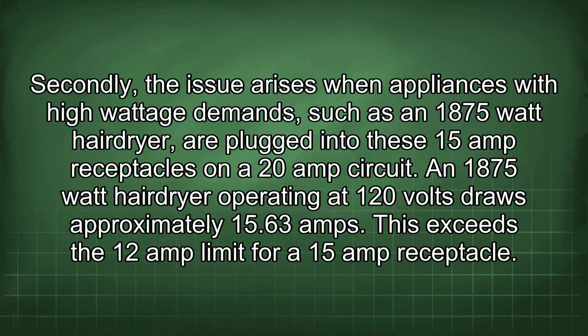Secondly, the issue arises when appliances with high wattage demands, such as an 1875-watt hairdryer, are plugged into these 15-amp receptacles on a 20-amp circuit. An 1875-watt hairdryer operating at 120 volts draws approximately 15.63 amps. This exceeds the 12-amp limit for a 15-amp receptacle.